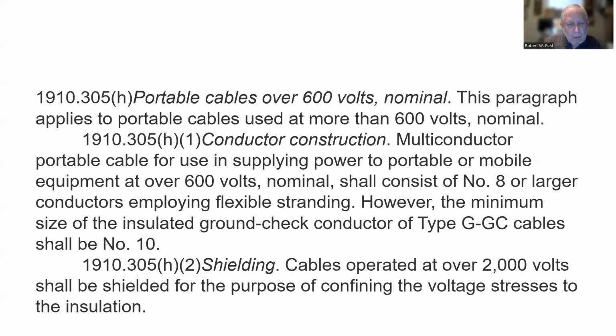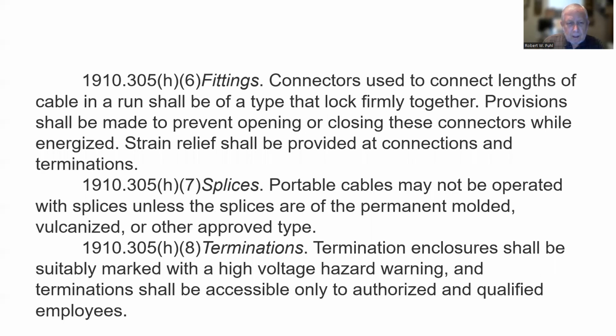Portable cables over 600 volts nominal. Again, if you're getting into something that's over 600 volts, you're probably an electrician and you probably want to read this. But this isn't a class for electricians, so we're not going to go over the over 600 volts. That's H6. H7, splices. Portable cables may not operate with splices unless the splices are of the permanent molded, vulcanized, or other approved types. I can't tell you how many extension cords I have found that I've thrown out, taken out of service. We did a big, huge butter company in Oklahoma City.